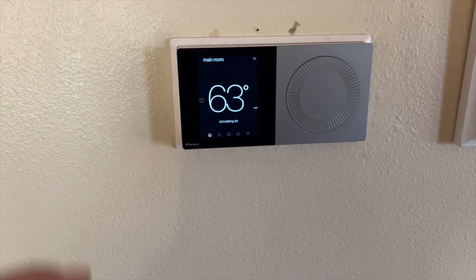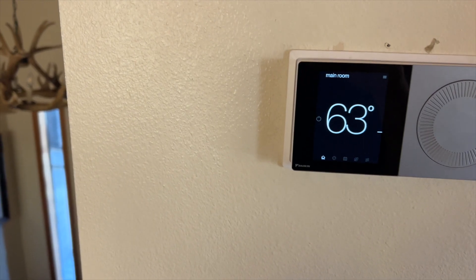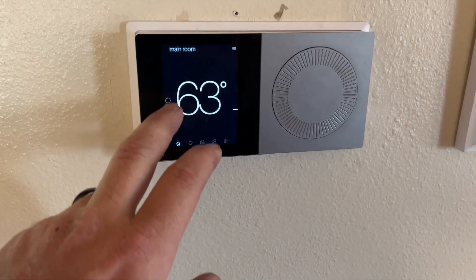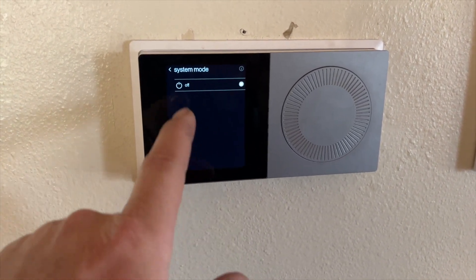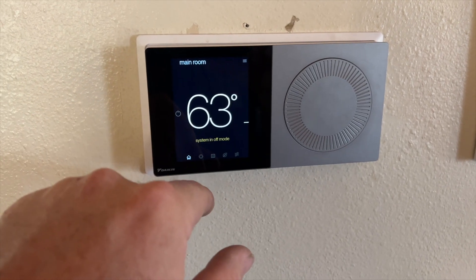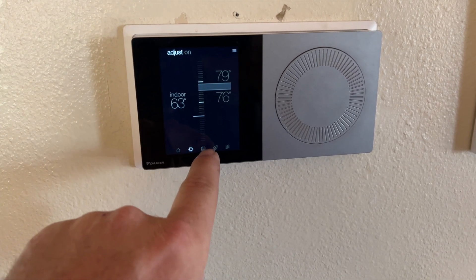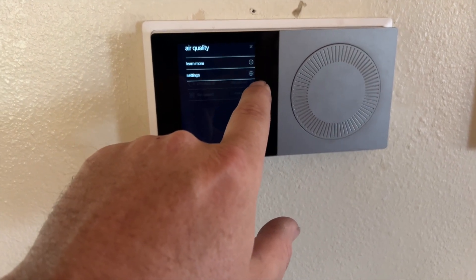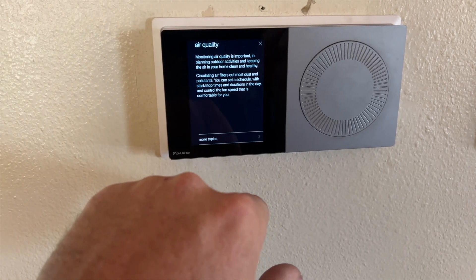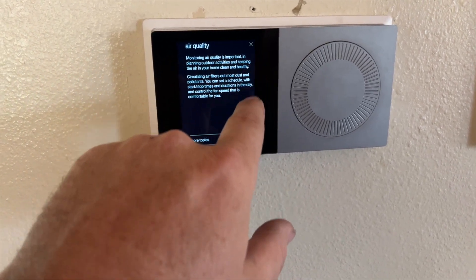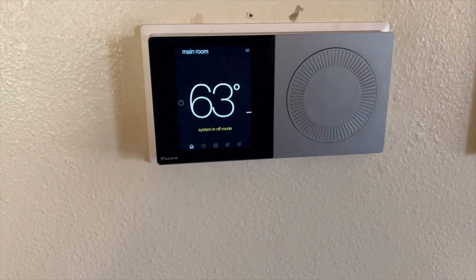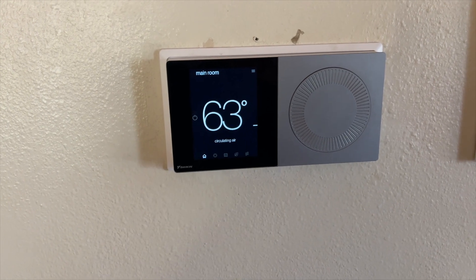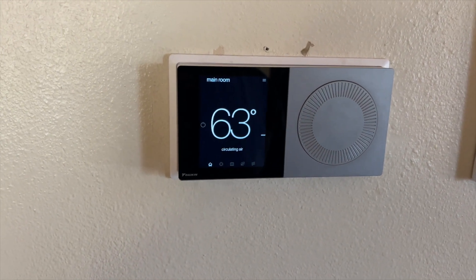We're back in the house with a no-heat and no-cool call. The system's not working at all — this is a Daikin by the way. When we hit power it doesn't give us any options, but we can cycle through everything else. No error codes showing, so we're going to reset and cycle the power to get it to reconnect. We probably have some kind of communication problem.